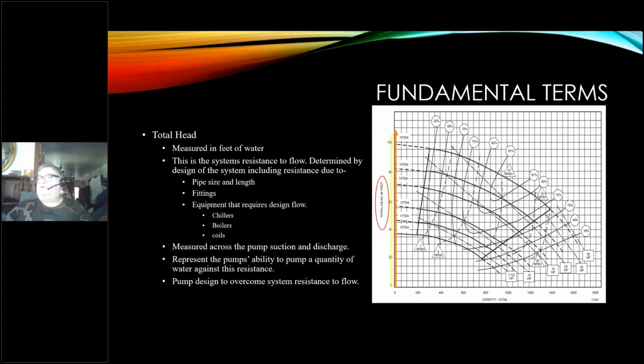So this is not your pressure differential out on the system. If you're looking at a control system that measures differential pressure, that's usually two-thirds of the way down the system. That's going to come up in a discussion later on, but this is not what we're talking about. This is right at the pump. So this is the pump's ability to overcome this resistance at different flow rates on the curve, the ability to pump a quantity of water against this resistance.